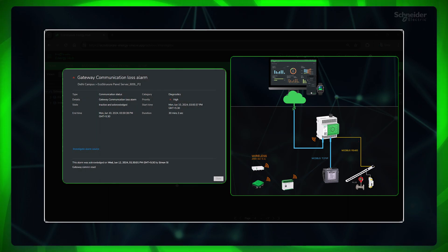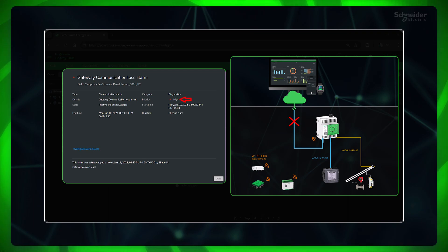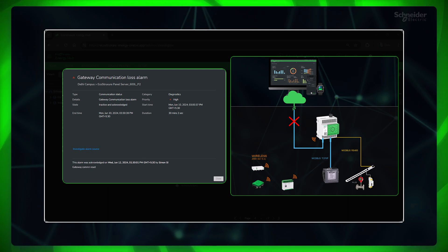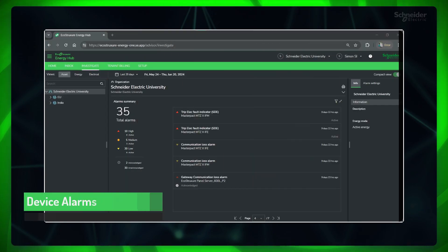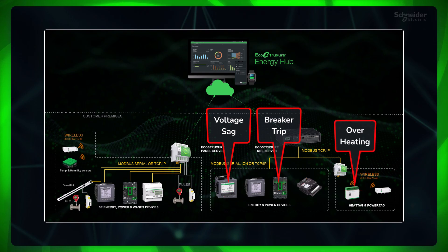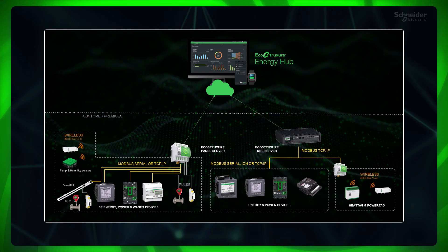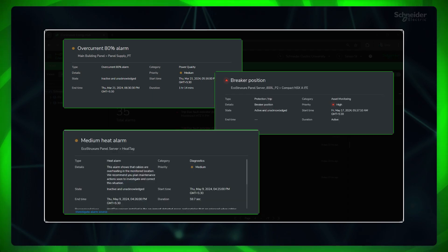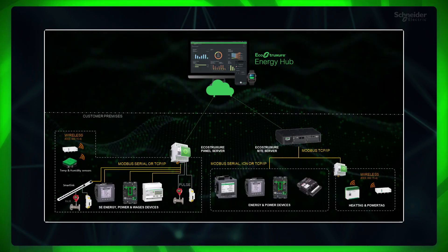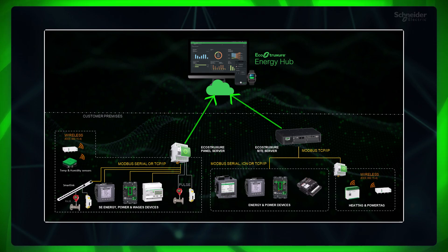When the communication between the gateway and Energy Hub is lost, a gateway communication loss alarm is generated with high priority. This alarm activates only when communication is interrupted for more than four hours, in order to minimize nuisance alarms caused by intermittent network availability commonly associated with cellular routers. For device alarms, these originate from the measurement or protection devices at the site and are generated and published by the gateway to Energy Hub. The publishing time to Energy Hub is up to 60 seconds for the panel server and under 30 seconds for the site server. This may vary depending on the latency in the customer network and internet speed.